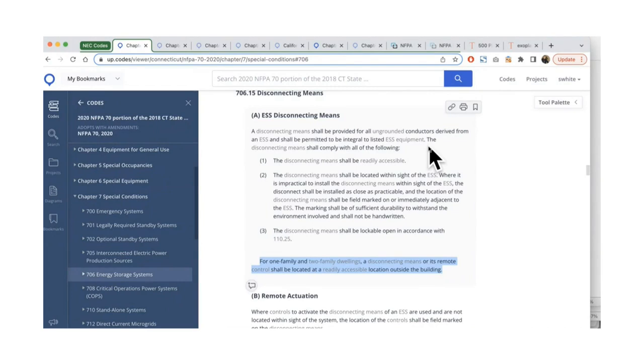Again, if there's an emergency situation, the fire department's out there pulling disconnects, they need to know that they're shutting all the power sources off in the building. And to me, that remote disconnect is a required means. Yeah, and if you had your energy storage system outside, that's even easier because you just turn it off right there, like your inverter. You're less likely to have your batteries outside. Probably a good idea, especially lithium ion doesn't work too well when it's snowing.